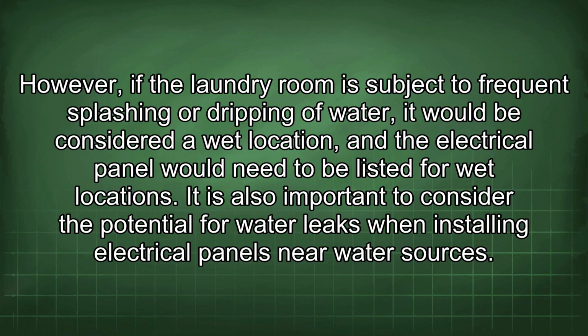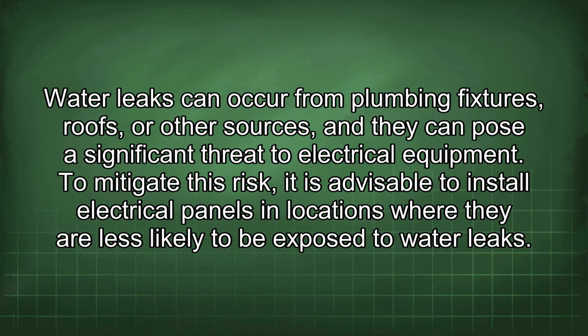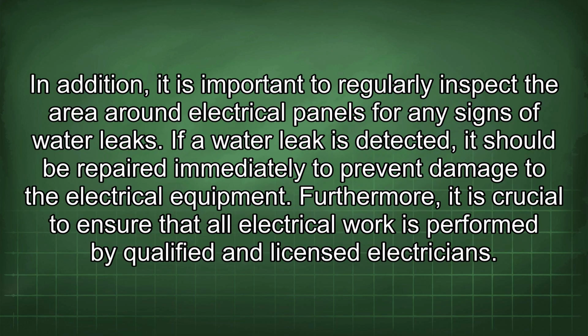It is also important to consider the potential for water leaks when installing electrical panels near water sources. Water leaks can occur from plumbing fixtures, roofs, or other sources, and they can pose a significant threat to electrical equipment. To mitigate this risk, it is advisable to install electrical panels in locations where they are less likely to be exposed to water leaks. In addition, it is important to regularly inspect the area around electrical panels for any signs of water leaks. If a water leak is detected, it should be repaired immediately to prevent damage to the electrical equipment.